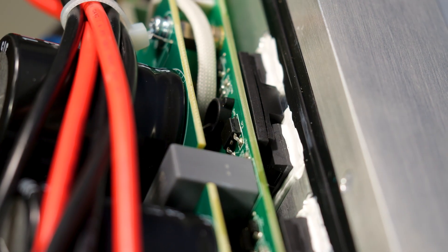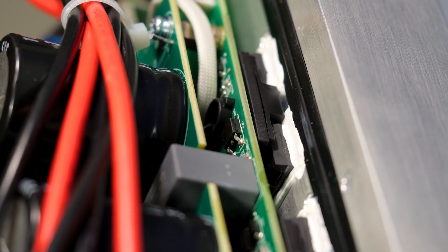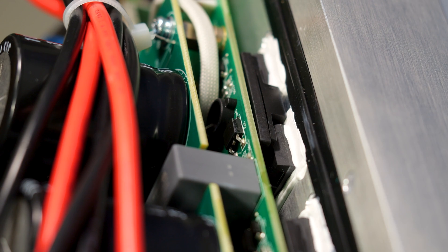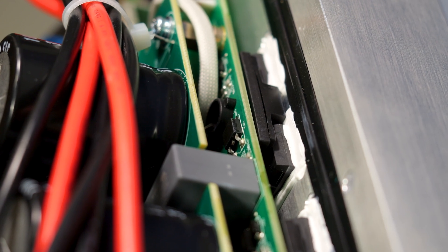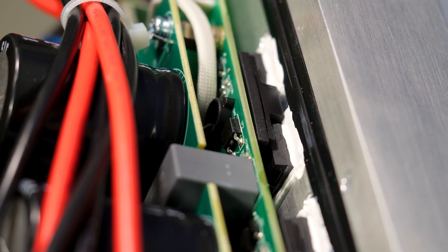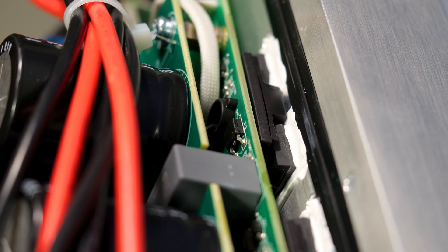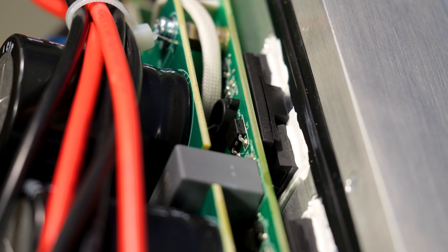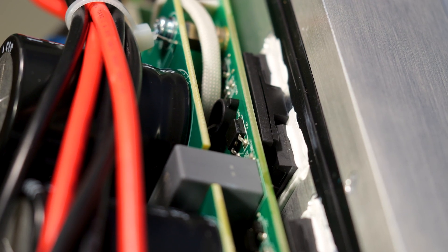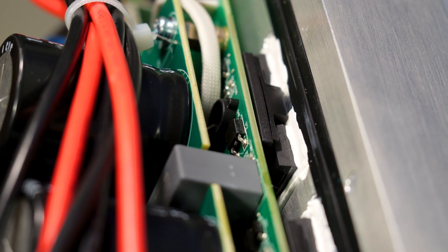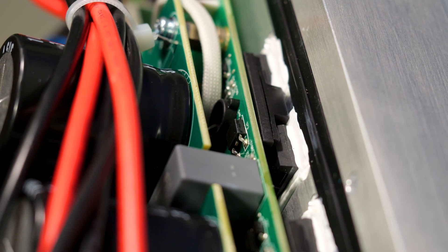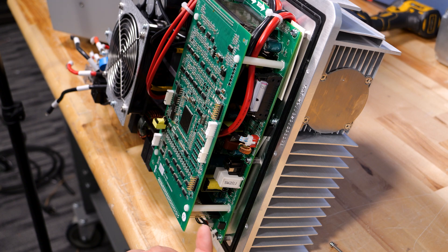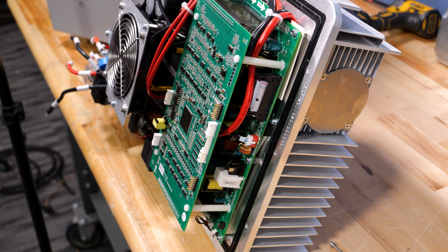All of the components that produce a lot of heat are mounted directly to the heat sink on the back of the unit. This is really good because it means the heat is removed directly from the enclosure instead of transmitted to the air within the enclosure and then transmitted out. This will lead to lower operating temperatures and a longer lifetime. Details like this put icing on the cake.